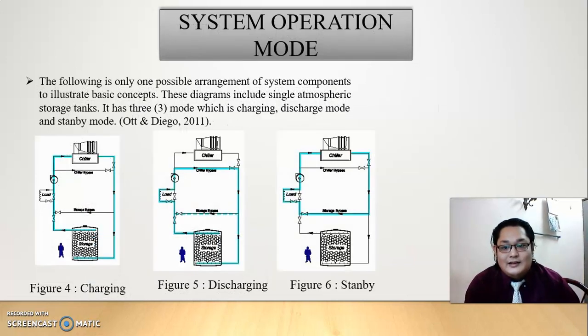The system operation mode has 3. The first one is charging, the second is discharging, and the third is standby mode. For charging, glycol is distributed in a storage tank surrounding the ice ball and subsequently cooled down to ice at a lowest temperature. For discharging, during the release mode, the same glycol solution in the storage tank flows around the ice ball and melts it. And during standby mode, the chiller may be utilized to immediately refresh the building without using an ice ball.